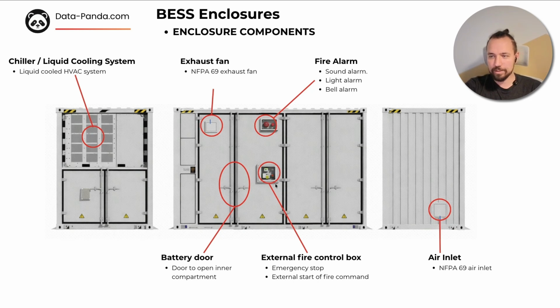So next one is the external fire control box. This is the box for the human interface to the fire system. It typically includes an emergency stop button. So like you press it and everything stops, disconnected. And the manual fire initiation system. This allows fire responders or operators to interact with the system without opening enclosures because we don't know what's inside.